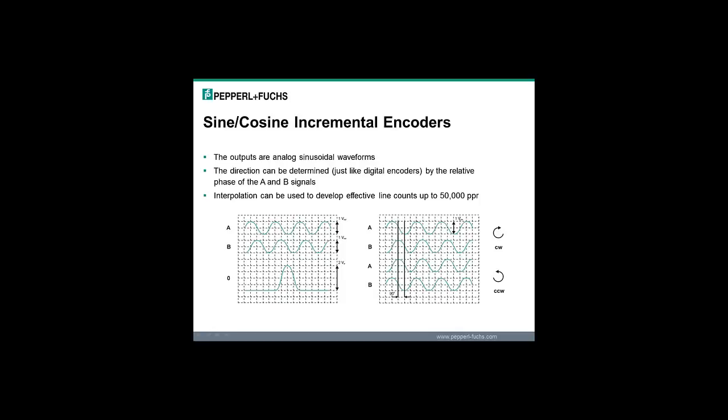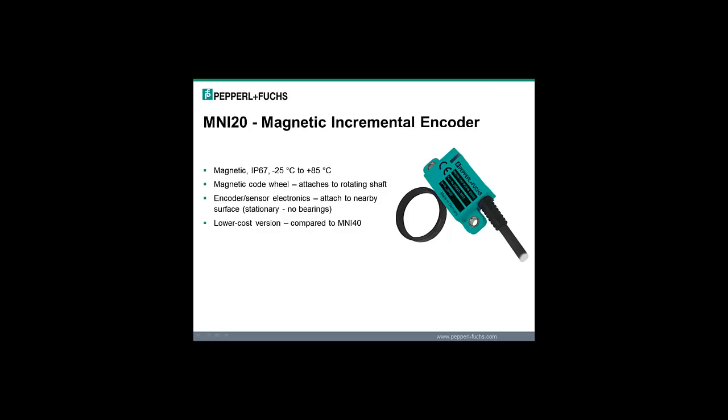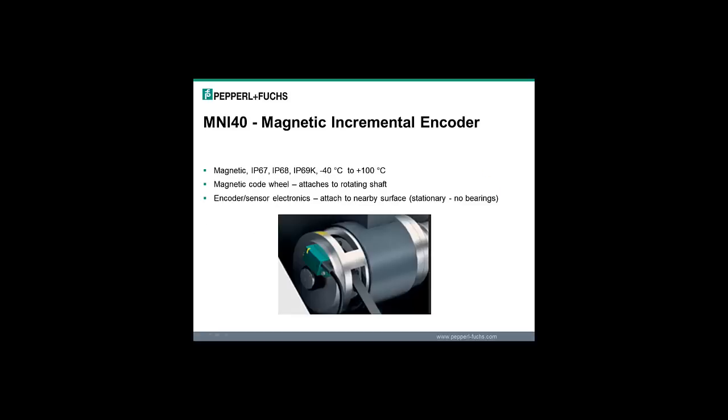The MNI-20 has two parts, the magnetic code wheel and the magneto-resistive sensor. It has no bearings or moving parts, so it has a very long service life. The MNI-20 is a lower cost version compared to MNI-40. The MNI-40 also has two parts, the magnetic code wheel and the magneto-resistive sensor. It has no bearings or moving parts, so it has a very long service life. Compared to the MNI-20, the MNI-40 has a higher temperature range, higher environmental rating, and a two-color LED to provide a clear indication of the magnetic wheel alignment and diagnostics.